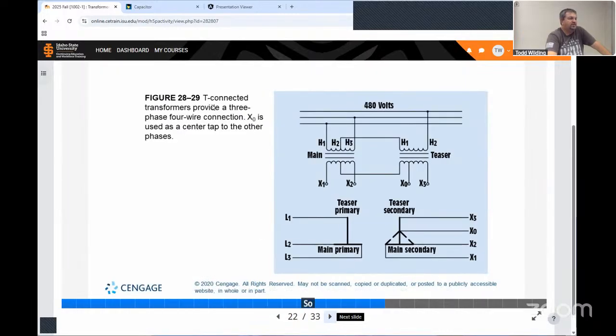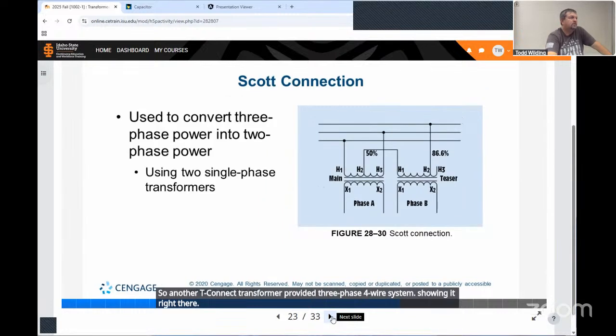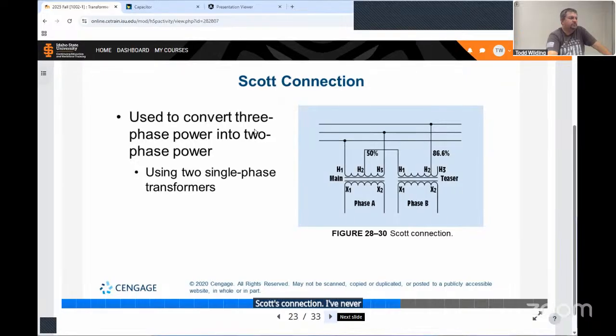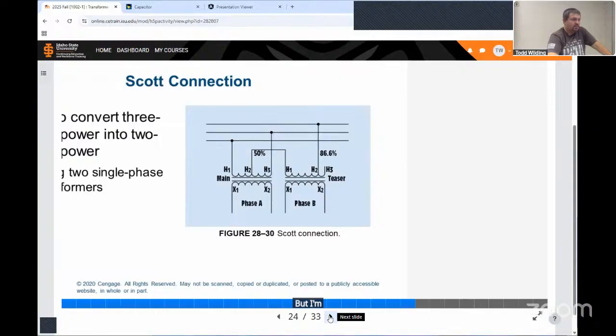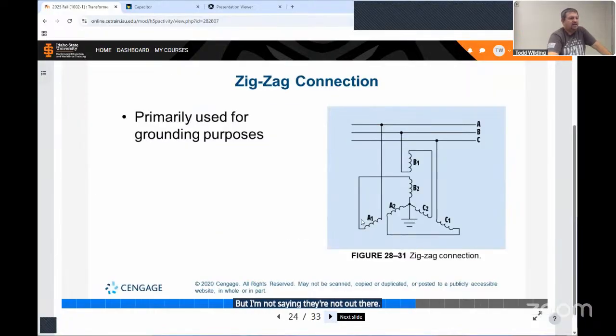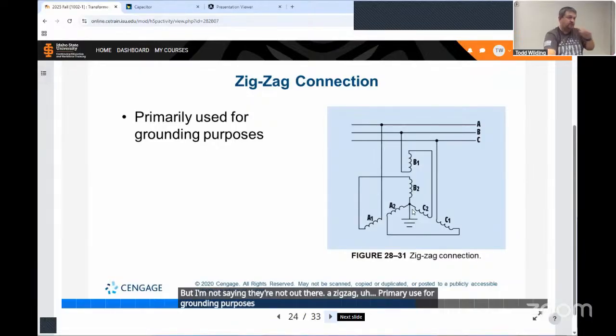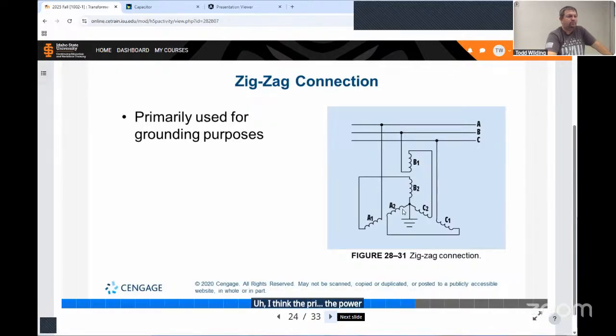Another T-connected transformer provides a 3-phase 4-wire system. Showing it right there. A Scott connection. I've never seen one of those used to convert 3-phase power into 2-phase power using 2 single-phase transformers. Again, I have not seen one of those, but I'm not saying they're not out there. A zigzag is primarily used for grounding purposes, to ground a transformer. I think the power company uses that more than we do.